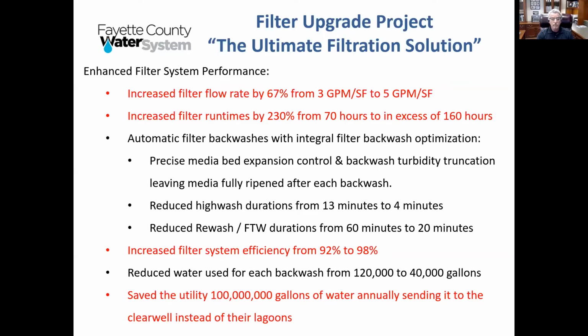Everything's automatic now. We reduced their high wash durations, the length of time that created that butte in the earlier screen that you saw, from 13 minutes. Well, we left them at just under 5 minutes, and through their own tuning that the operations has worked on to perfect their backwashes, they've now reduced that to about 4.5 or 4 minutes at this point, which is really almost 10 minutes of reduction every backwash, which saves them about 62,000 gallons of water per backwash just in the high wash step. But it also reduces, when you do that, the need to continue to rewash the media when you're trying to place it back in the service.